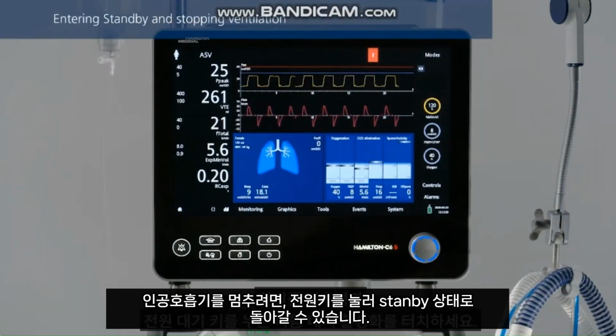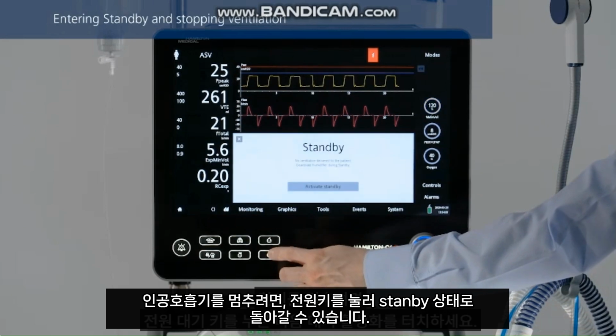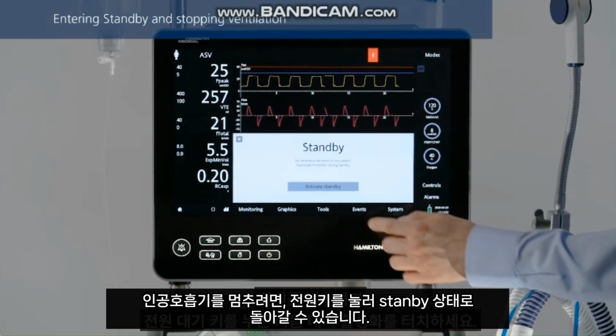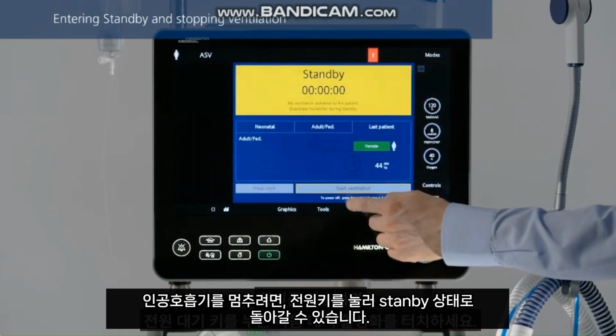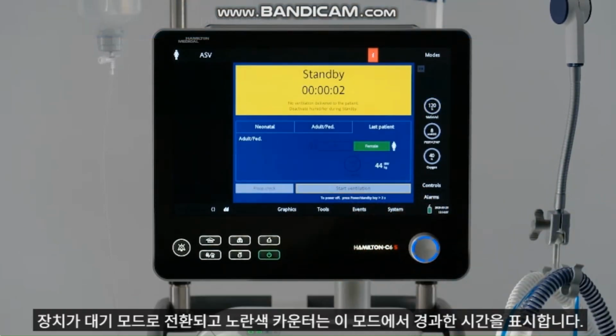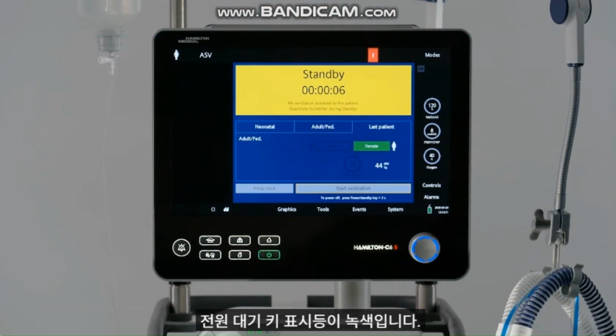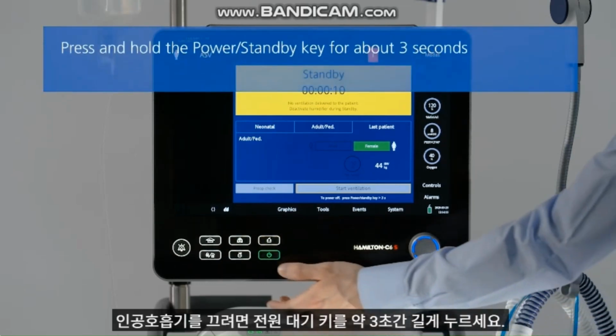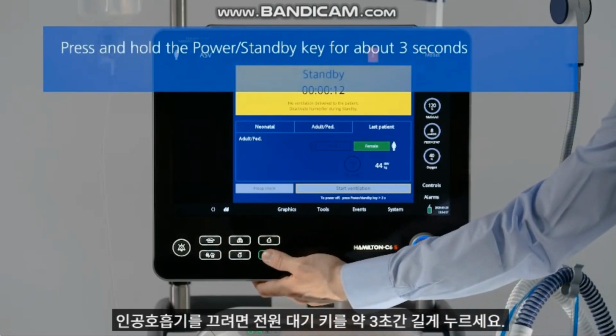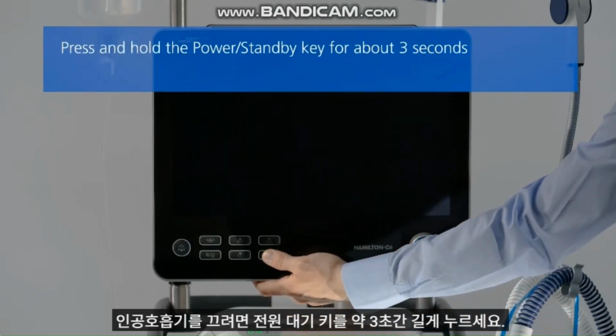To stop ventilation, press the Power Standby key. Then, touch Activate Standby. The device enters standby and the yellow counter shows the time elapsed in this mode. The Power Standby key light is green. To turn off the ventilator, press and hold the Power Standby key for about 3 seconds.